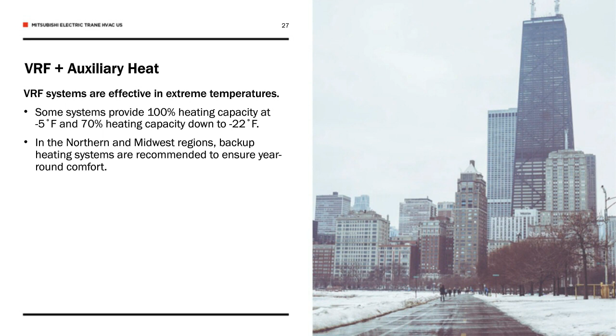Here's an application and an example of a VRF system with auxiliary heat integrated through a VRF manufacturer's provided controls. VRF controls can be configured to activate backup heat when it's required in those extreme situations. As required by the application, the VRF controls can manage and sequence almost any kind of supplemental heating, including hot water baseboard or electric, into the ductwork to work as a backup and supplemental provider of heat in extreme situations.